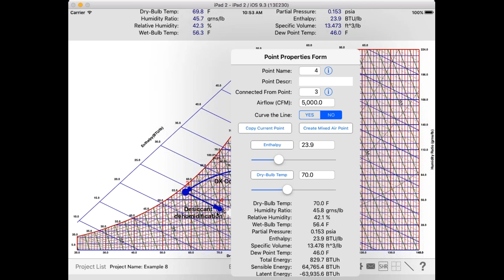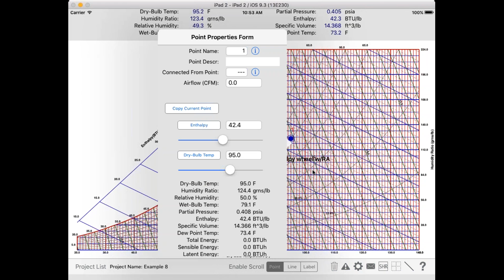Now, how much cooling did we save by doing that pre-cooling? Well, if we were going to DX cool all the way from the outside air point to down here without any pre-cooling using an enthalpy wheel, you do the math, subtracting the enthalpies times 4.5 times the CFM airflow of 5,000, you'd have about 34 tons of cooling. However, instead, we're doing the math from this point, taking the enthalpy from this point to here, it's only 17 tons. So pretty much half the tonnage requirements due to that enthalpy wheel. So by plotting the points on the chart, we're able to see that.